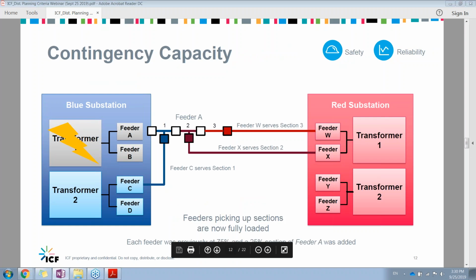That's what we're showing here now: the feeder that went out of service was broken up into 3 different sections as designed by the planning criteria, with open points between sections 1, 2, and 3. The connection points to these adjacent feeders are closed in order to re-energize and restore those customers on feeder A.